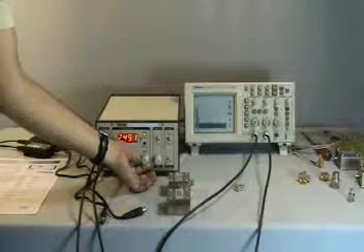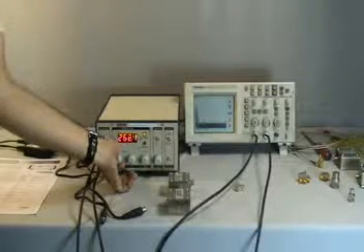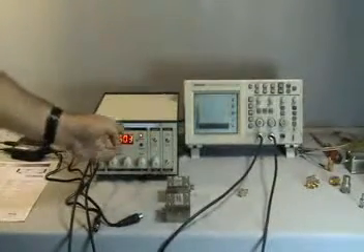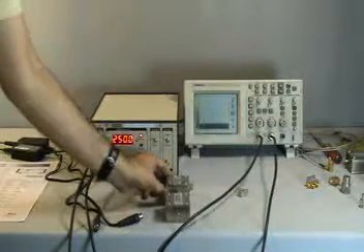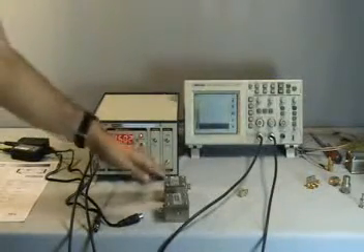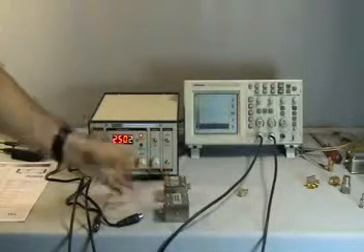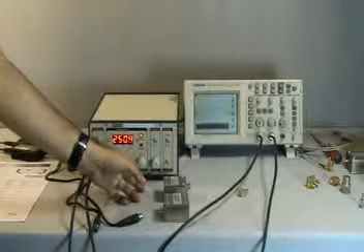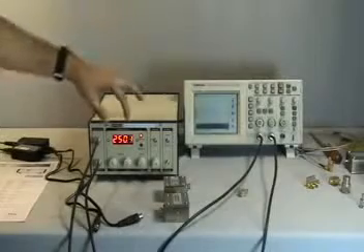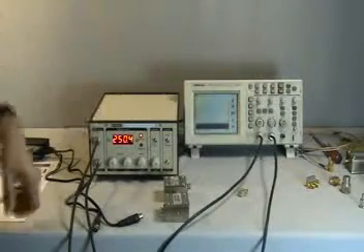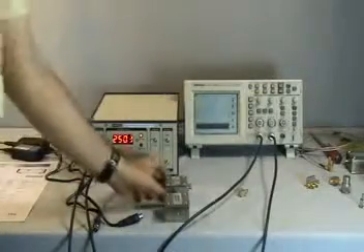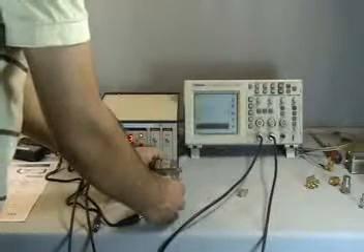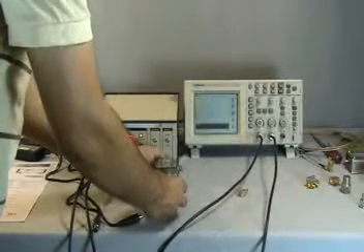We set the center frequency to roughly 250 megahertz, and this becomes our frequency of observation for measurement of the noise figure of this particular amplifier under test. The sweep we can reduce. We may reduce it sizably so that we are only observing the noise figure at one particular frequency of our interest.